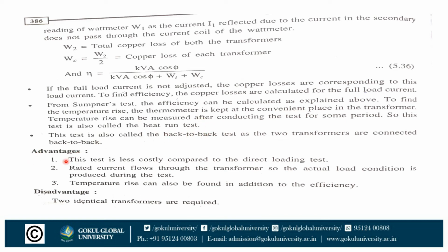Now, advantages of this test. First one is this test is less costly compared to the direct loading test. Second one is rated current flows through the transformer, so the actual load condition is produced during this test. And third one is temperature rise can also be found in addition to the efficiency. Disadvantages: only one disadvantage is that two identical transformers are required.